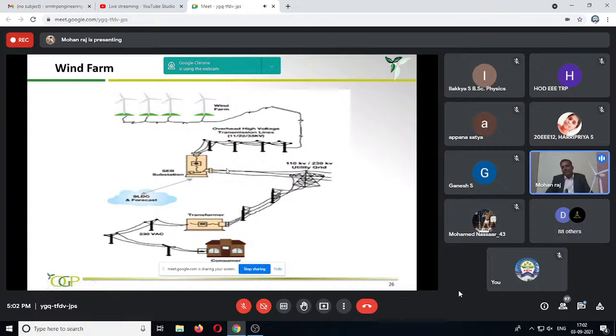So if you want to transfer power from Kanyakumari to Chennai, and you transfer the power at 33 or 11 or 66 kV level, the transmission loss will be more. That's why we need to step up the voltage. For that purpose, substations are used. Further, this 33 kV, 22 kV, 11 kV, 66 kV is converted to 110 kV, 230 kV. Nowadays, 400 kV lines are available to transfer power to various parts of the state and various parts of the country.